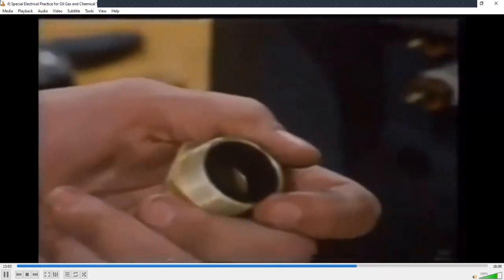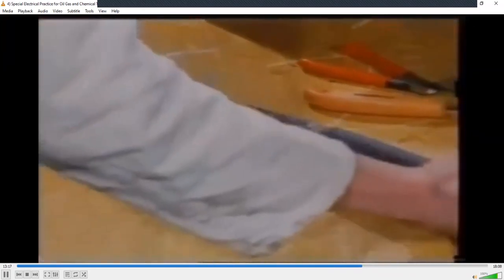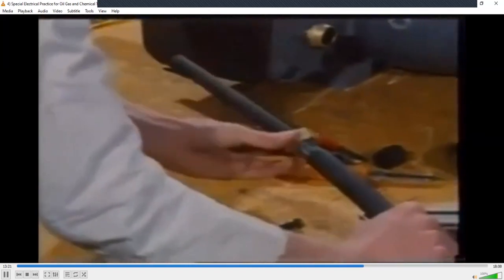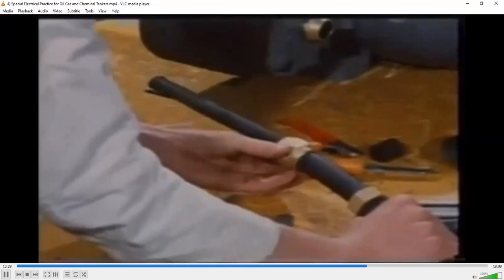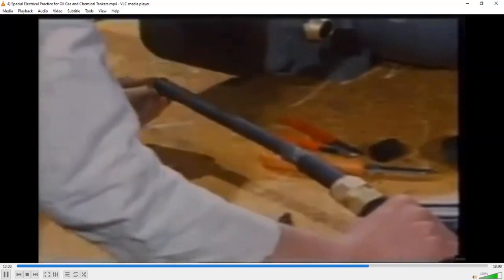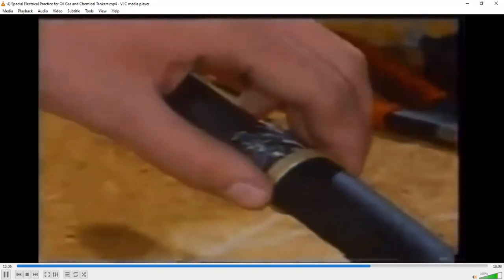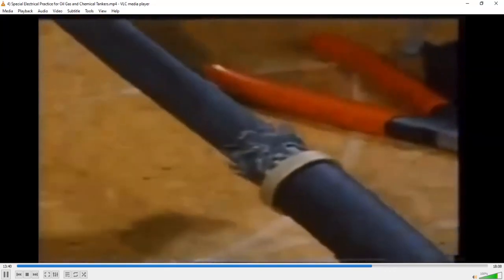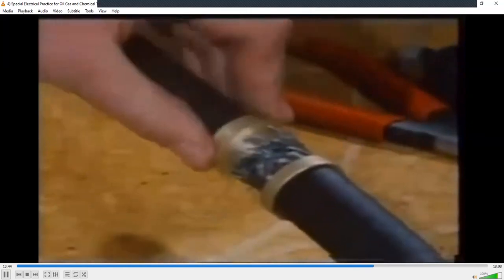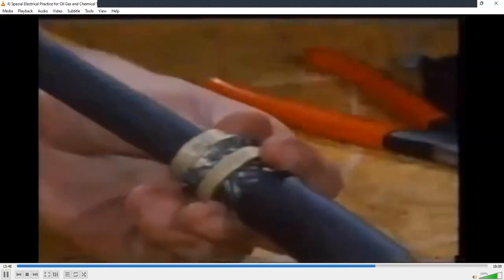Use special flame-proof glands which have longer threaded flame paths and rubber seal rings with extended hold on the cable, forming another flame path. Carefully dismantle the cable gland and secure the threaded base unit in the terminal box. Fit the lock nuts on the cable, then the double rings for gripping the steel armouring. Fit the conical rings below and above the loose armouring, like this, ready for tightening.